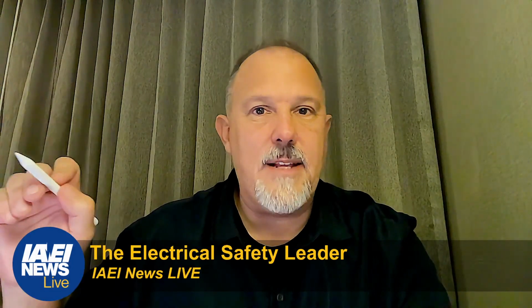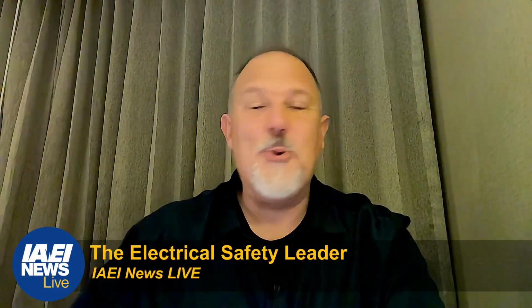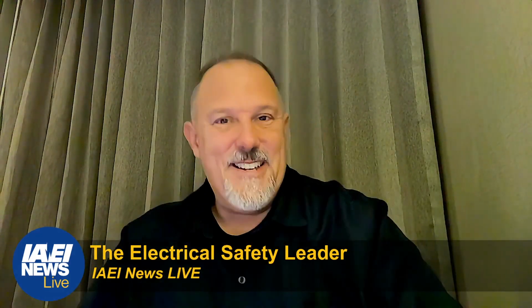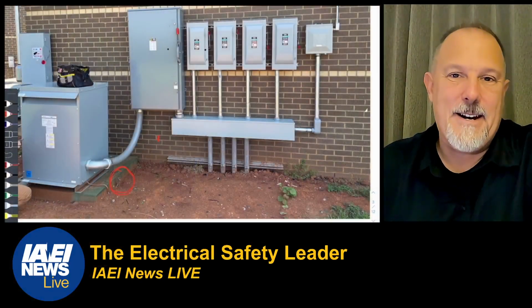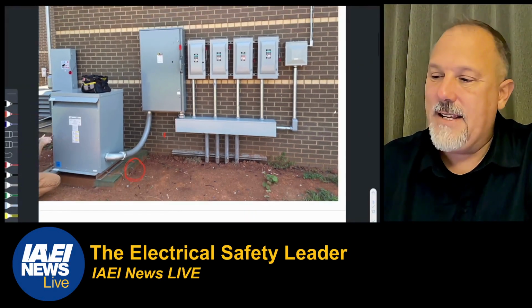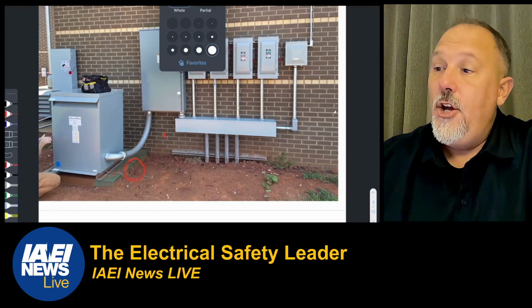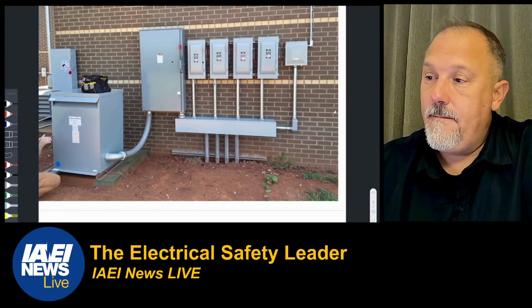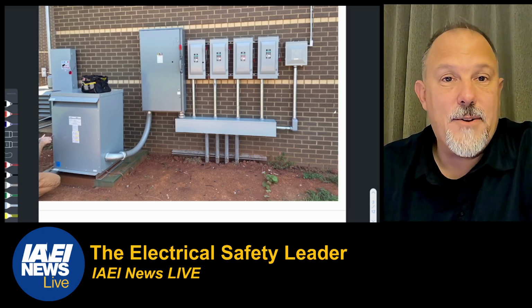I'm setting the stage, because moving forward, you're going to see this example, and we're going to walk through the grounding and bonding of all of this. We're going to walk through the transformer, primary protection, secondary protection, the conductor sizes, the available fault currents. We'll calculate the incident energy at the safety disconnect switch and at each of these 100 amp switches. And at that trough, we're going to use this and abuse it and make a really cool series of videos to walk through. And I'm going to need your help to make us accurate. Share your knowledge.